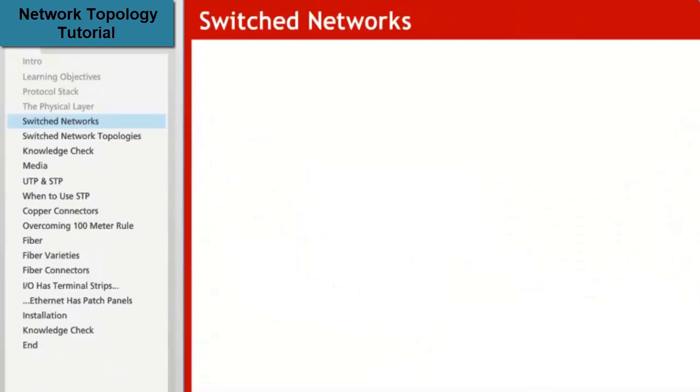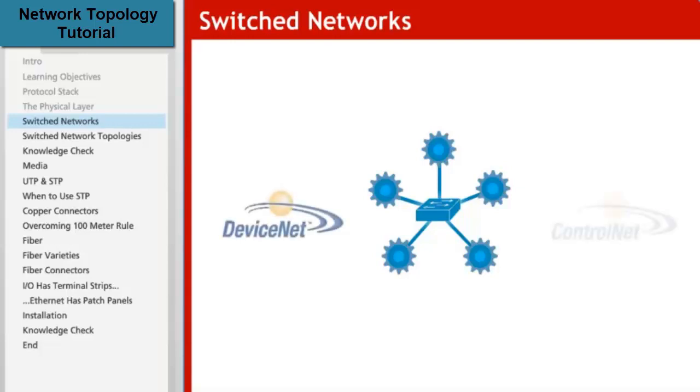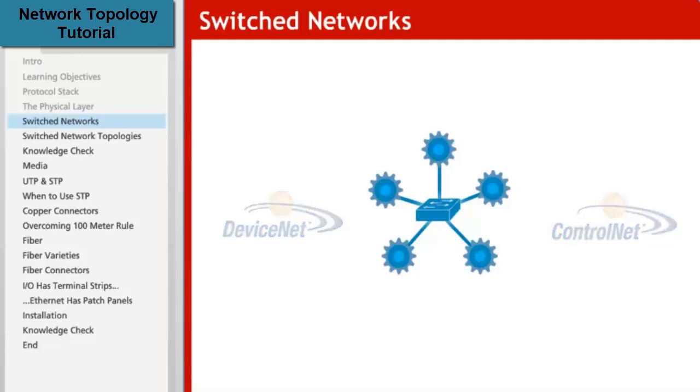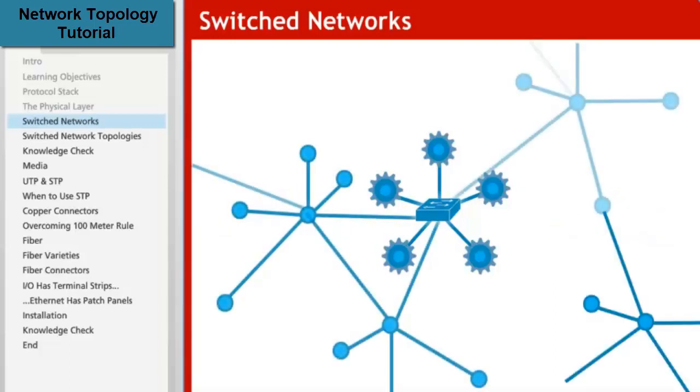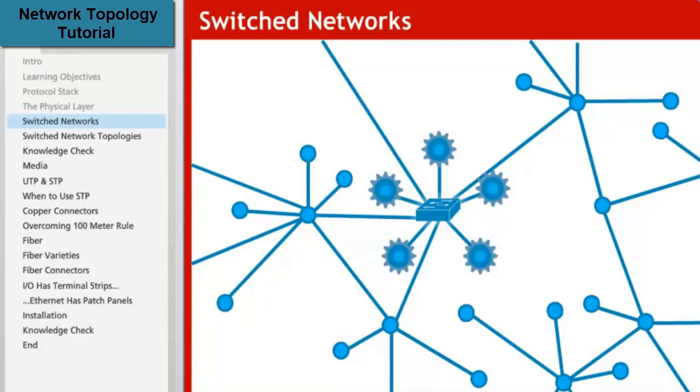Because of this simple rule, the fundamental building block of Ethernet networks is a star configuration with multiple end devices connected to a switch in the center of the star. As networks grow, the switches themselves need to be connected to each other to enable communications throughout the facility. Herein lies the big difference between Ethernet and other networks. DeviceNet and ControlNet do not use active devices like switches. Therefore, those networks are limited to a specific maximum number of devices. With Ethernet and its active switches, small networks can be connected together to form larger networks and can eventually be connected to the internet, creating a very large network indeed. And so it is that the use of switches sets Ethernet apart.